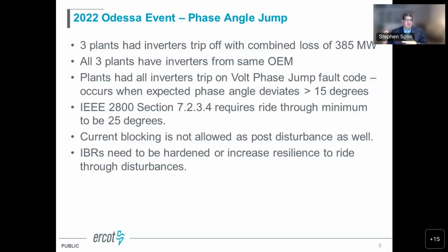Now, if you set it too high and it's going to cause some equipment concerns or there's some impact to the system, those things have to be taken into consideration. But I just want to point out, one of the lessons learned we've had is if you're given a requirement, you're just going to park your relays right above it. And in general, resilience should be the principle rather than just compliance right above a particular set point.